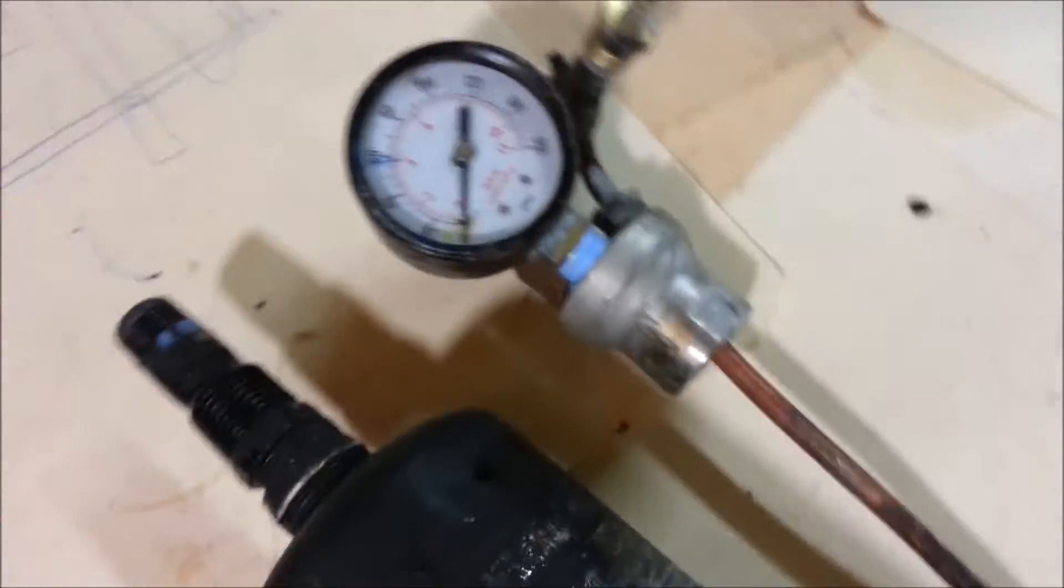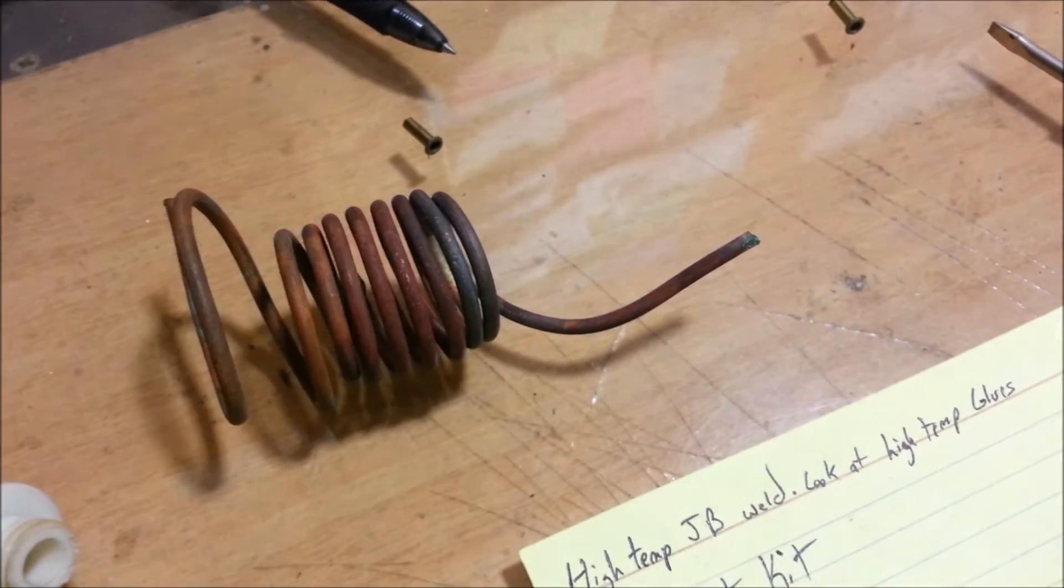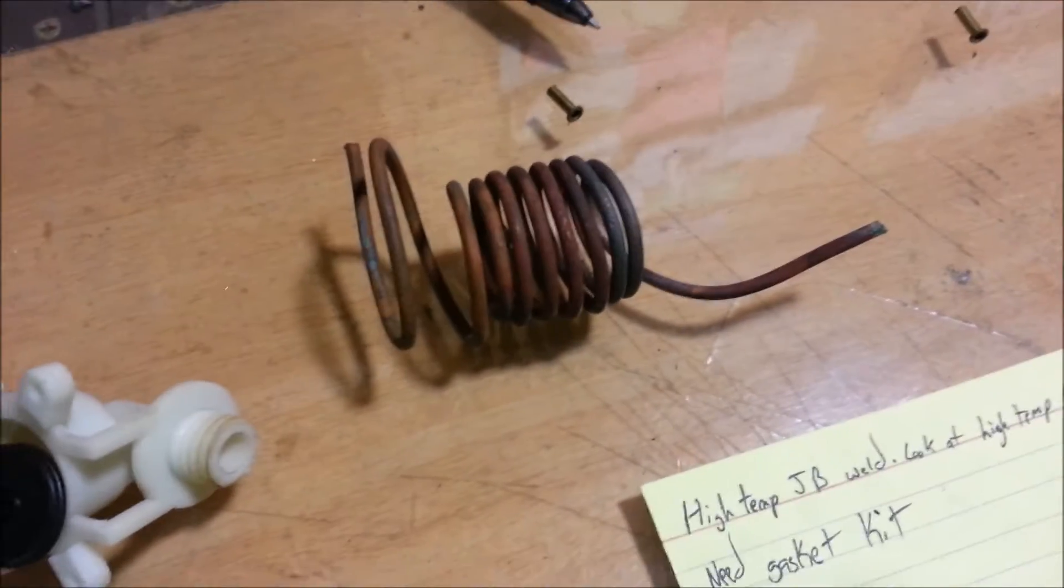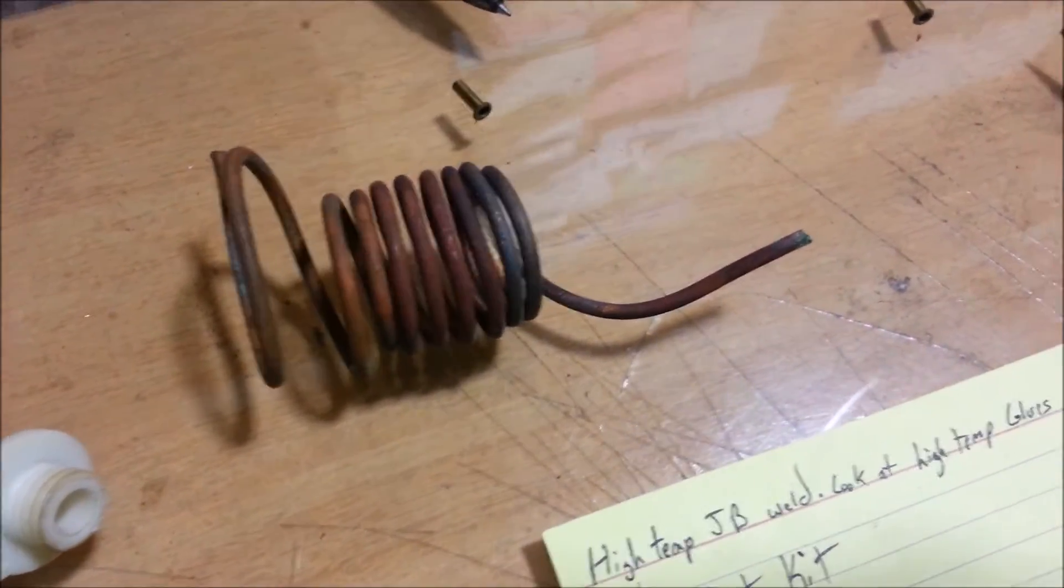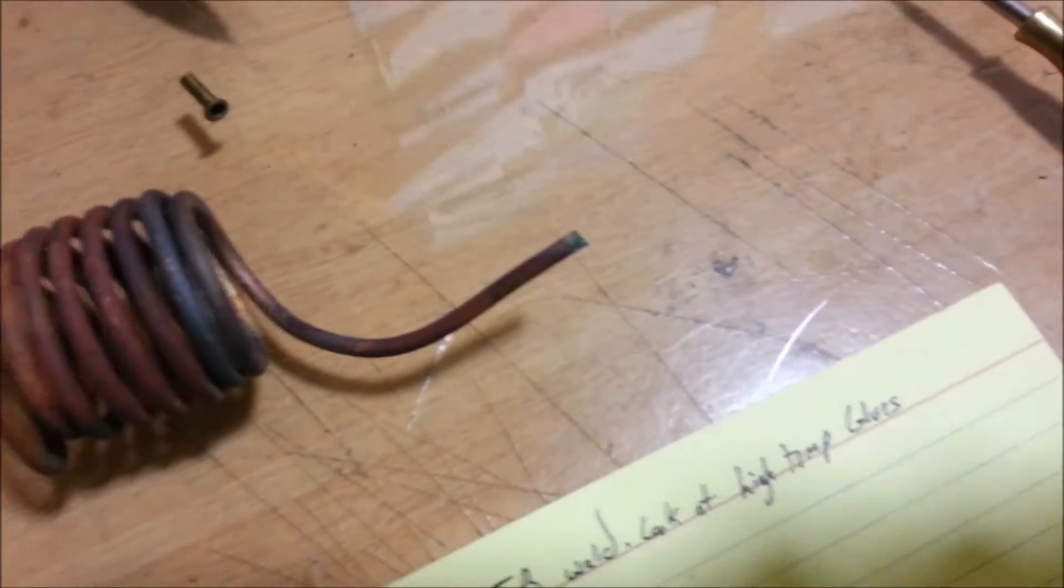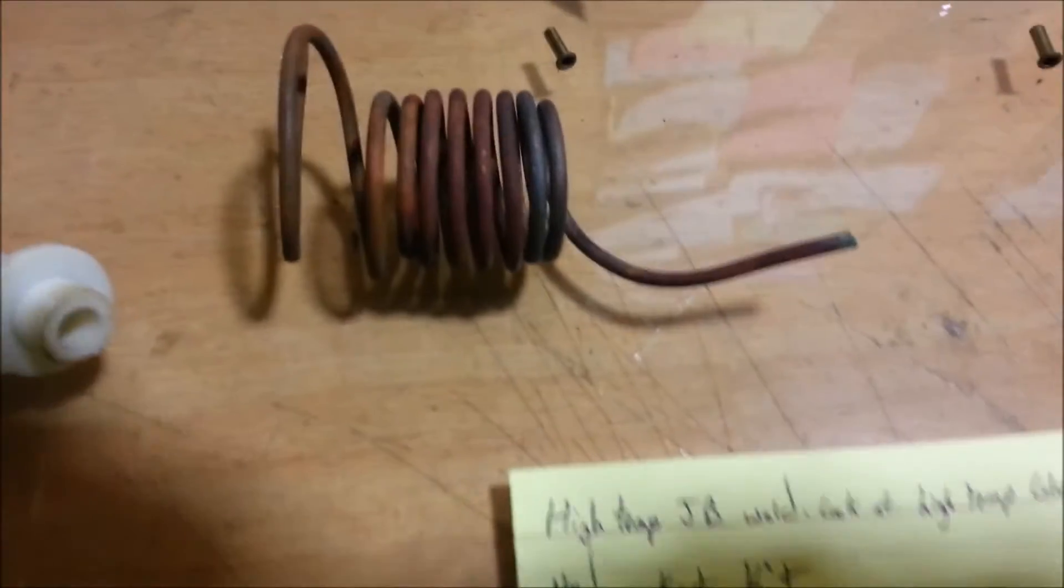By charging this tank with air, I was able to inject water into this coil, and something Gary told me that's called vapor lock began to happen. Around 50 PSI wasn't always enough pressure to keep water moving through the coil. The steam pressure developed by steam liberation was inhibiting flow.